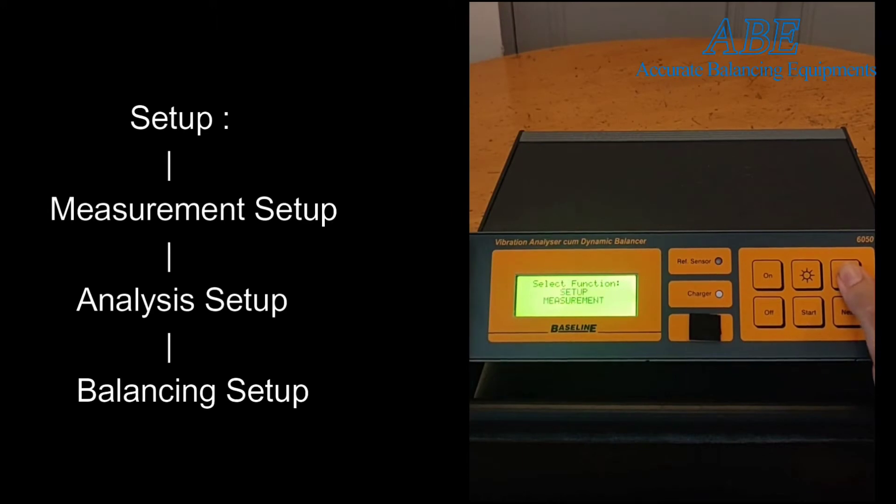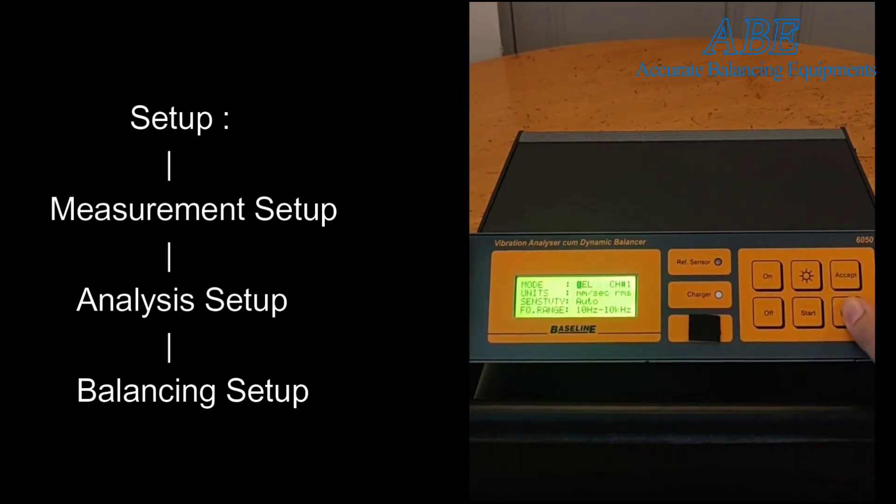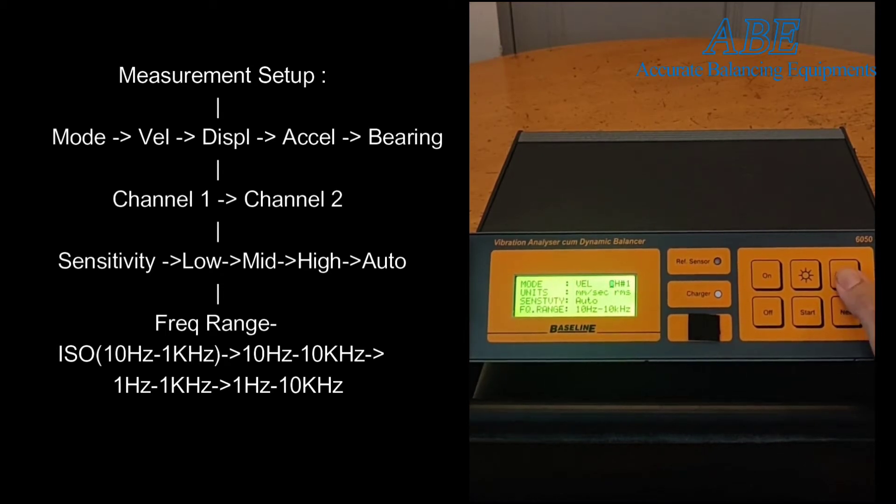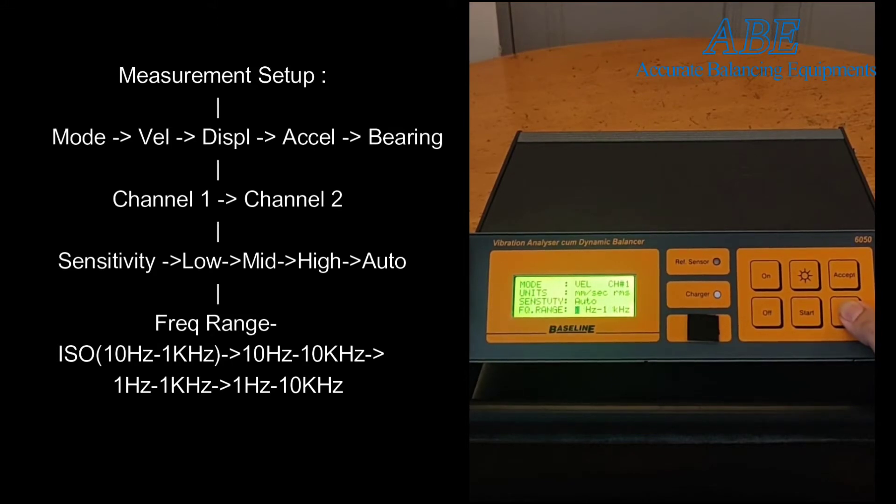Inside setup, you can configure the 6050 for measurement, analysis, and balancing. Inside measurement setup, you can firstly select the vibration units, then toggle between channel 1 and channel 2 of the instrument. The cursor then moves to the sensitivity, which cycles between high, low, mid, and auto. Next, the frequency range may be selected from the options.